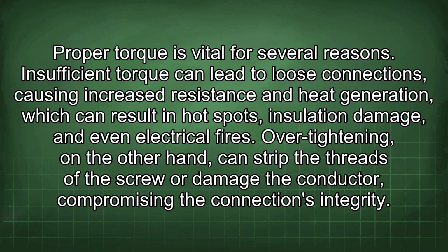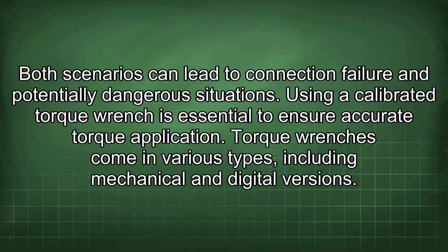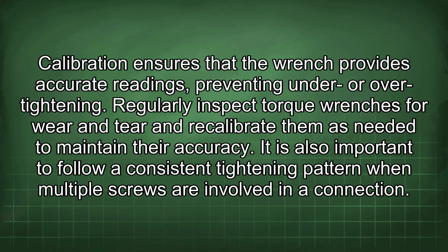Proper torque is vital for several reasons. Insufficient torque can lead to loose connections, causing increased resistance and heat generation, which can result in hot spots, insulation damage, and even electrical fires. Over-tightening, on the other hand, can strip the threads of the screw or damage the conductor, compromising the connection's integrity. Both scenarios can lead to connection failure and potentially dangerous situations. Using a calibrated torque wrench is essential to ensure accurate torque application. Torque wrenches come in various types, including mechanical and digital versions. Calibration ensures that the wrench provides accurate readings, preventing under or over-tightening. Regularly inspect torque wrenches for wear and tear and recalibrate them as needed to maintain their accuracy.